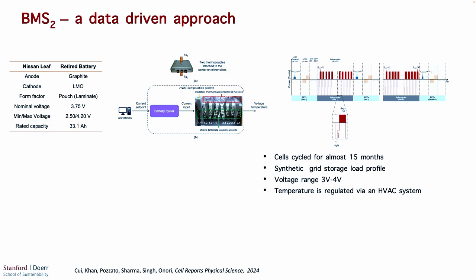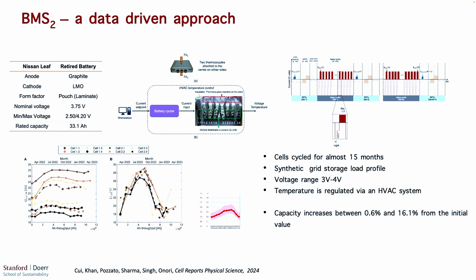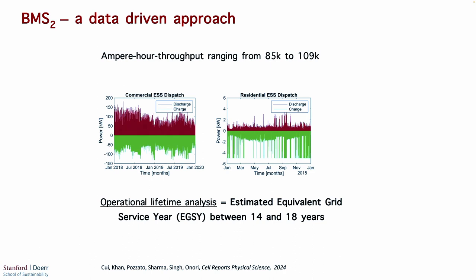Our aging campaign consisted of aging cycles and periodic reference performance tests needed to objectively evaluate the system health. One striking result is that if you look at the residual capacity of the second life batteries over a period of 15 months or so, the capacity not only doesn't decrease, it actually increases, and the increasing capacity follows the temperature envelope. So after these 15 months of operation, corresponding to around 100,000 ampere-hour throughput, those batteries had enough capacity left.